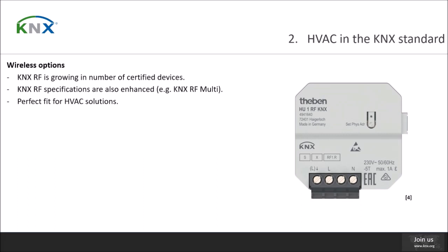Additionally, there are other improvements in the KNX specifications that allow KNX RF couplers to behave as segment couplers so that you can extend an existing KNX twisted pair line installation without changing physical addresses and the related work on the ETS. For this reason, KNX RF is an excellent option to be used in HVAC solutions.